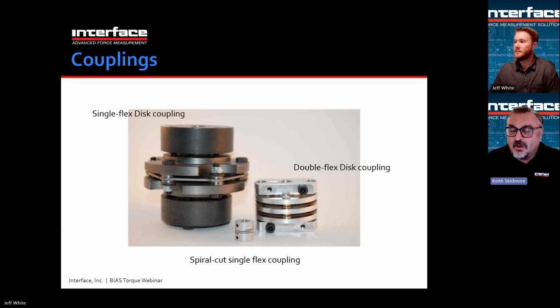And on the right, we have a double flex disc coupling, similar design as the one to the left, but it has two disc packs separated by a plate. Again, very well-defined flex points right in the center of each disc pack. They're separated by distance, so the coupling on the right can allow for some radial misalignment, whereas the coupling on the left does not displace at all radially, very, very minimally, but it does deflect quite nicely in the angular direction.